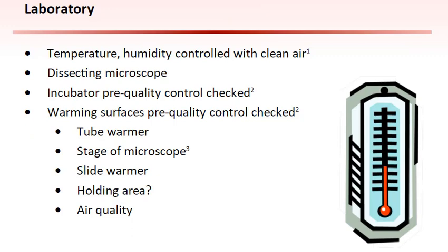The embryology laboratory should be a room with controlled temperature and humidity so that sensitive, temperature-controlled devices such as incubators and warming surfaces do not undergo fluctuations or unusual offsets due to the ambient conditions in the lab. The room should be located conveniently to the operating room or procedure room to minimize exposure of follicular aspirates to uncontrolled environmental conditions during transit to the laboratory.